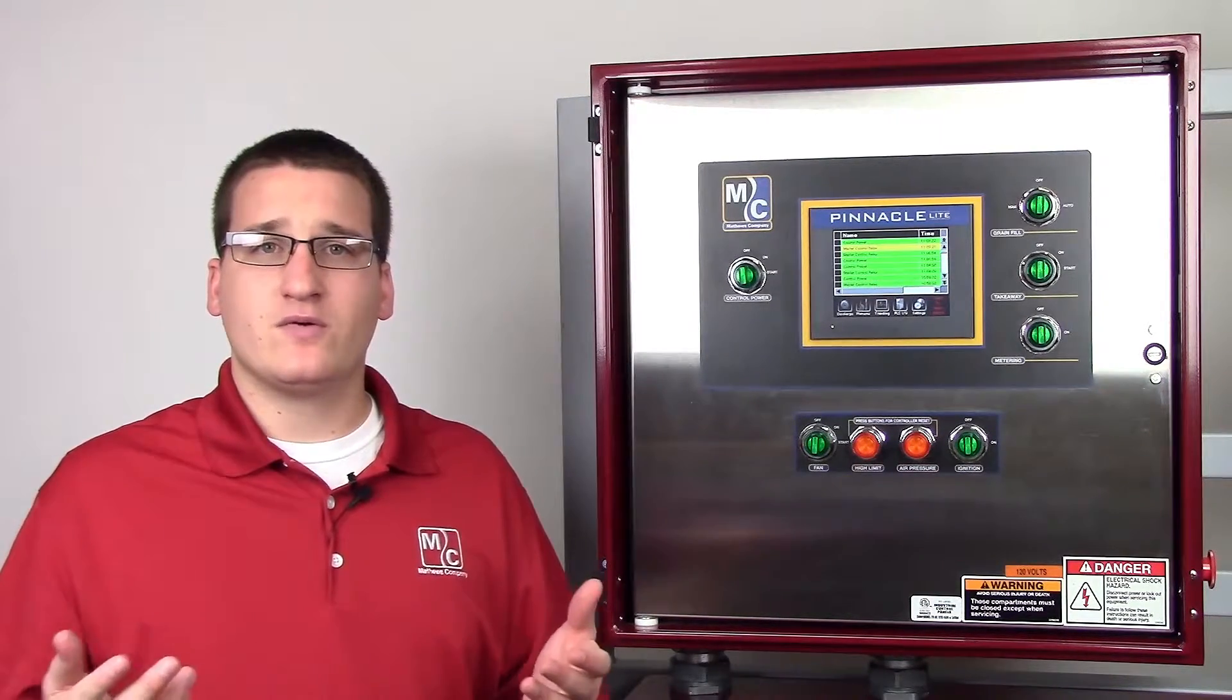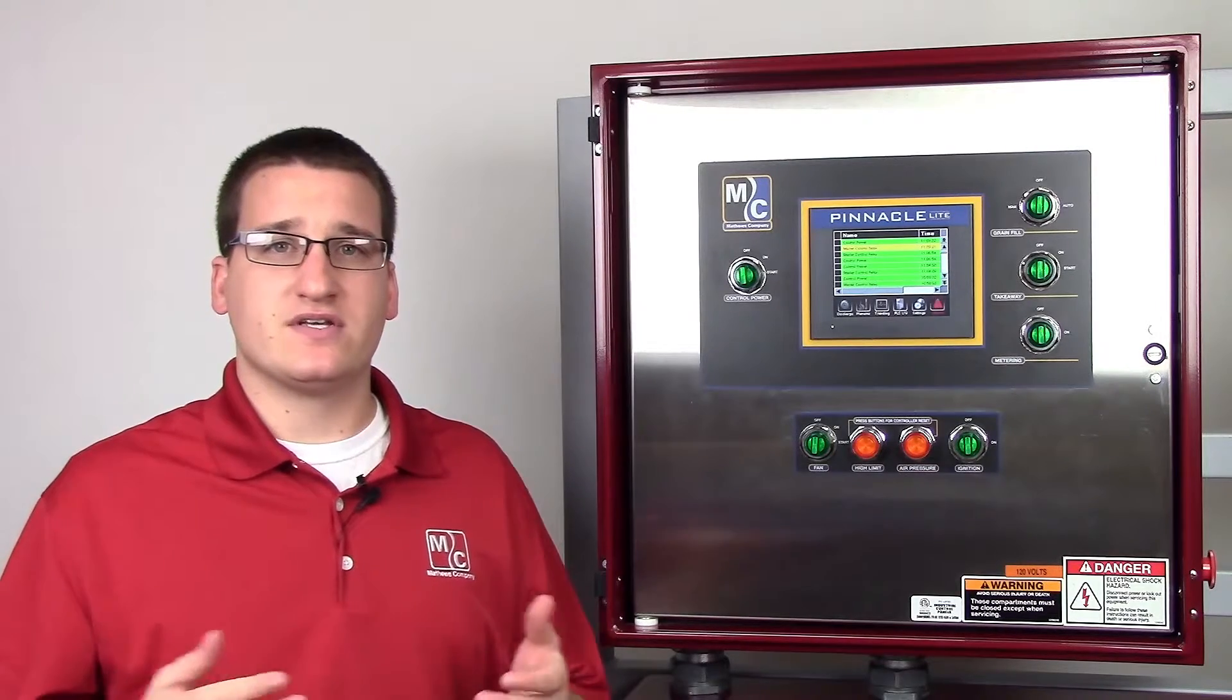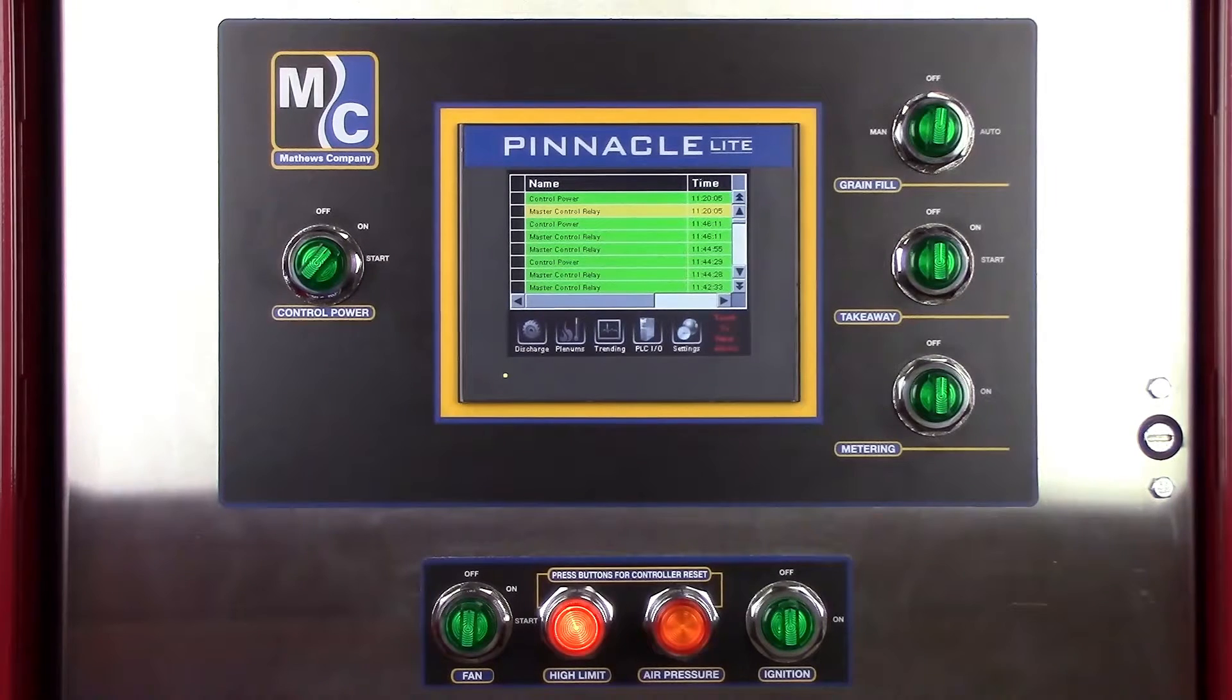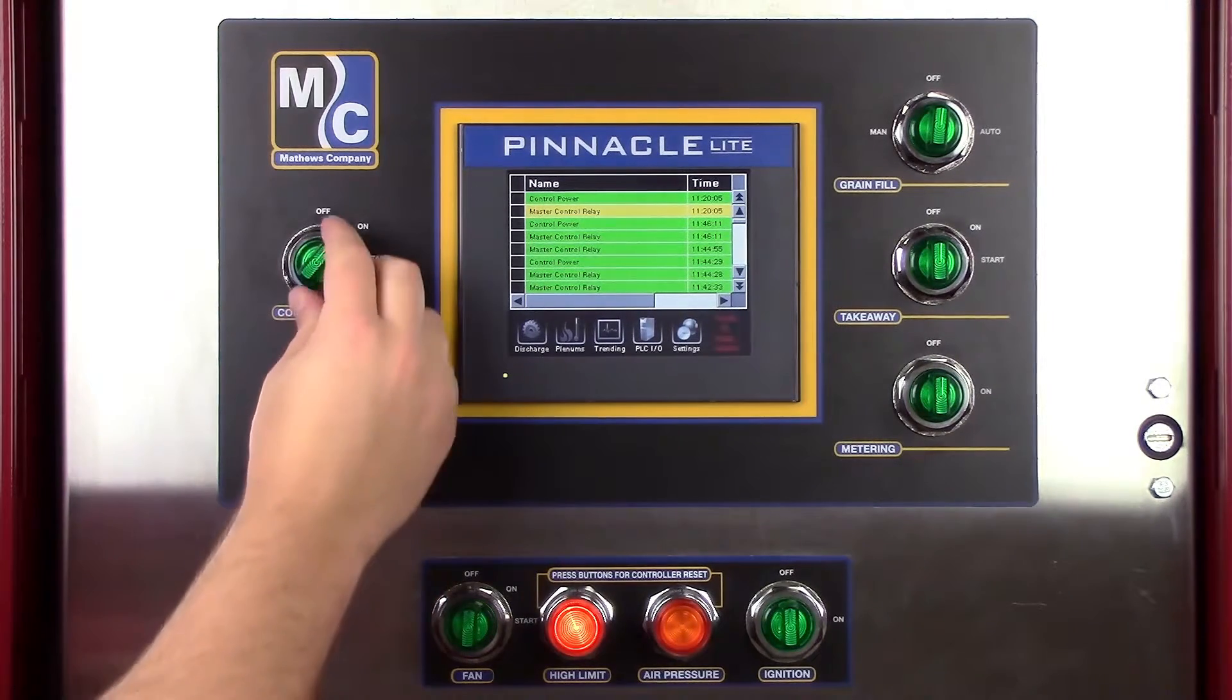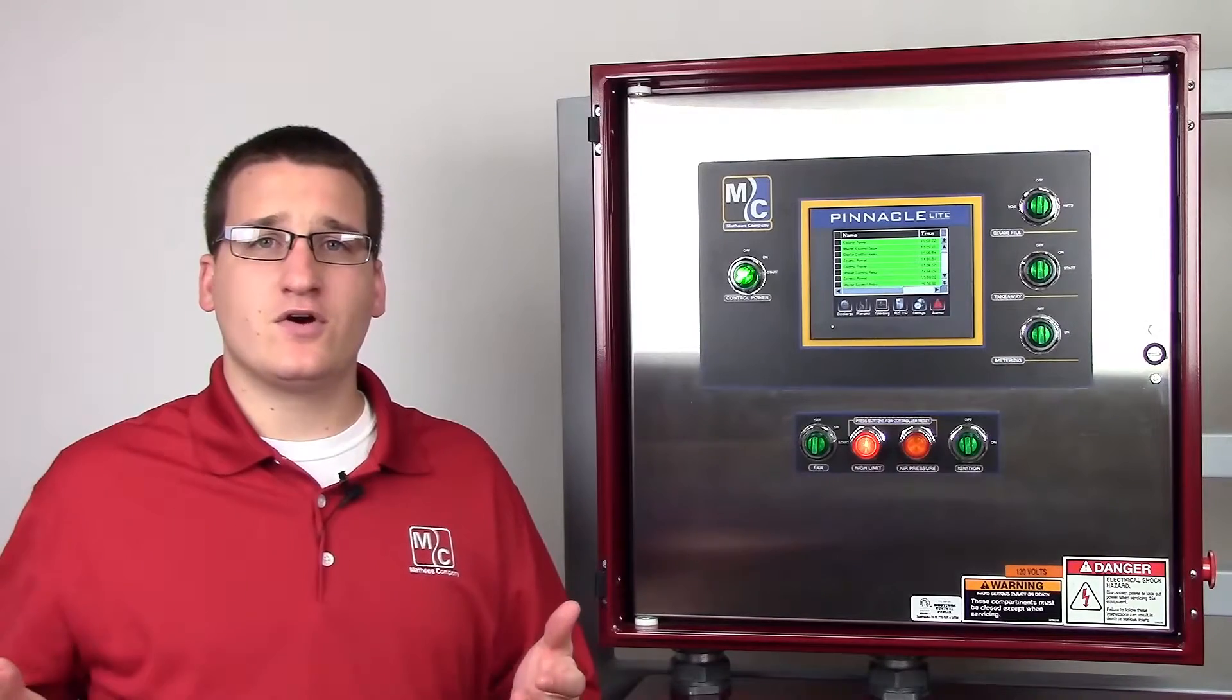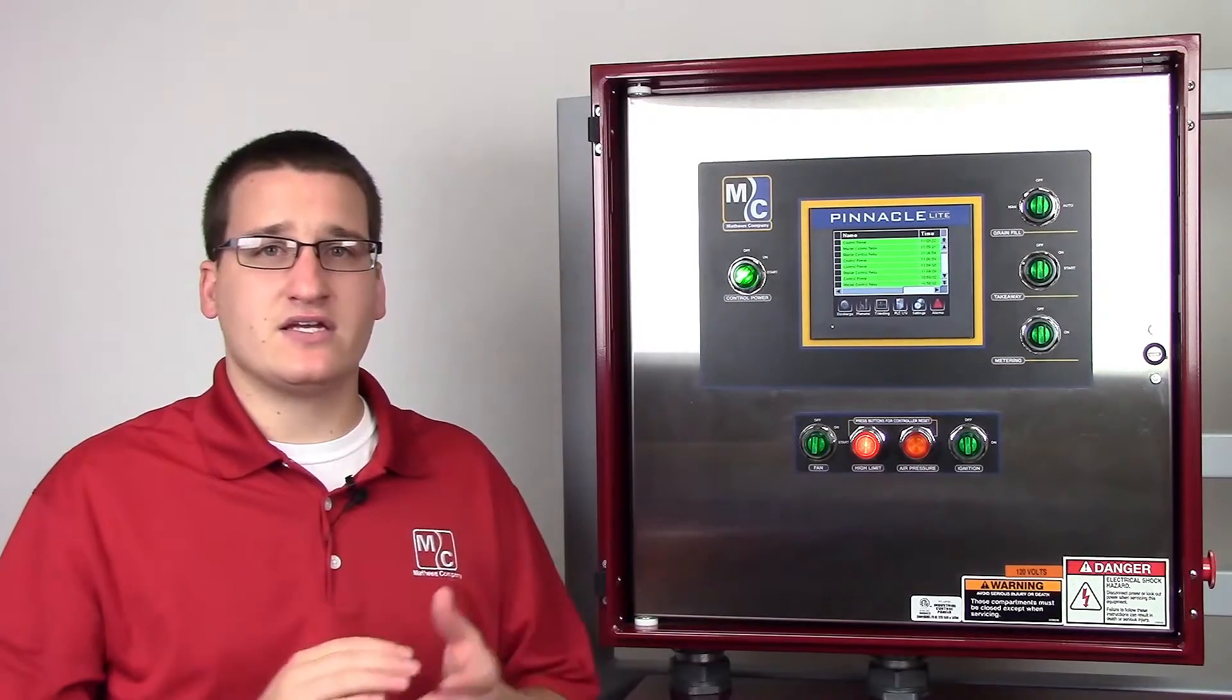This should clear all alarms except for the master control relay. In order to clear this alarm, we'll turn the control power switch to the on position and then momentarily to the start position. You'll know control power is on if the light is illuminated.